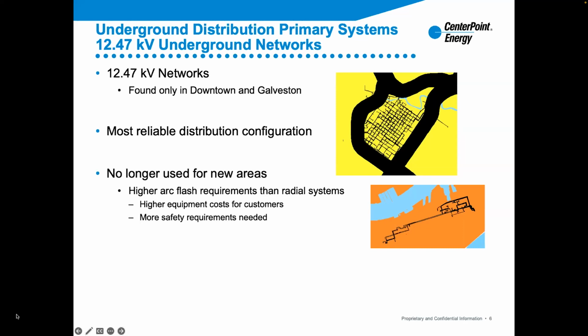The highly dense network does create higher costs for customers in the area because of increased arc flash, and they have to abide by higher safety standards. So to maintain affordable electricity for our customers, we could make them install 24,000 amp rated panels, but that's excessive cost. So instead we use a very small, specialized area with highly controlled underground vaults in order to serve these customers.